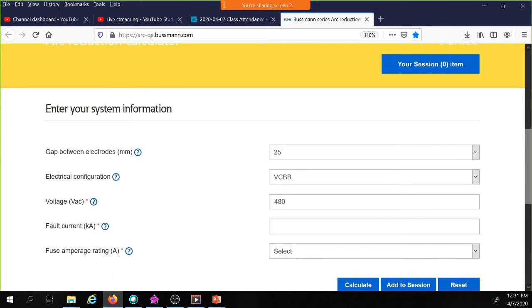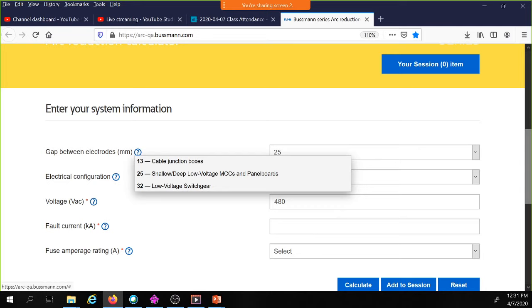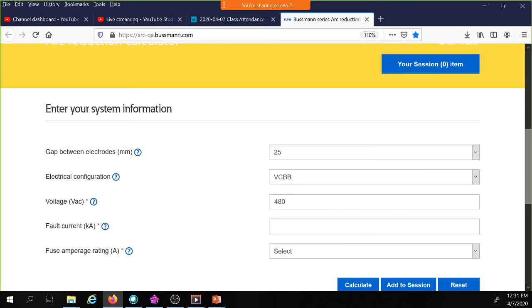I'll show you what it does. It works off of IEEE 1584, the 2018 version, the latest version. You have the gaps between electrodes, and I gave you what 1584 tells us. They use 25 millimeters for shallow, low voltage MCCs and panel boards, 32 for low voltage switchgear. Most of the engineers I talk to will use 25 for switchboards as well. That's why we defaulted to 25.